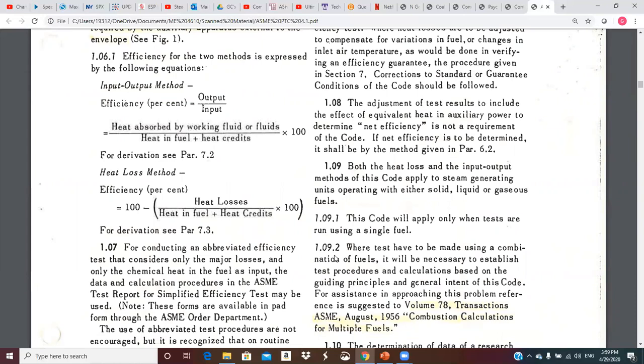Efficiency for two methods is expressed by the following equation. So we actually have two methods of efficiency determination. One is what's called the input-output method. And efficiency is output divided by input, common sense definition that you all know. And output is described as heat absorbed by working fluid or fluids. And then the input is the heat in the fuel, the chemical energy in the fuel, plus heat credits. And credits are other energy types that enter the control volume of the boiler.